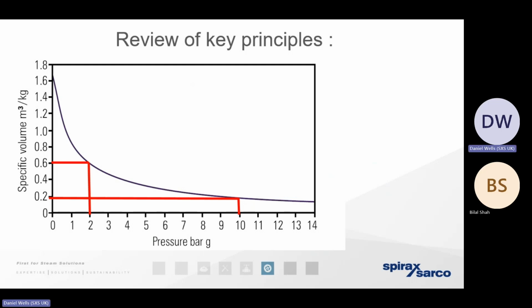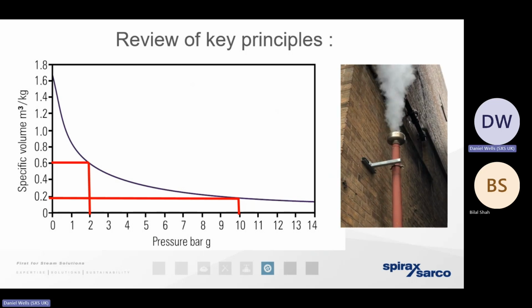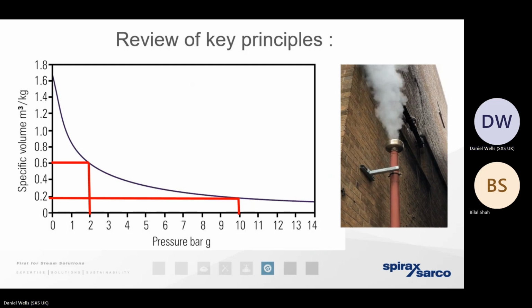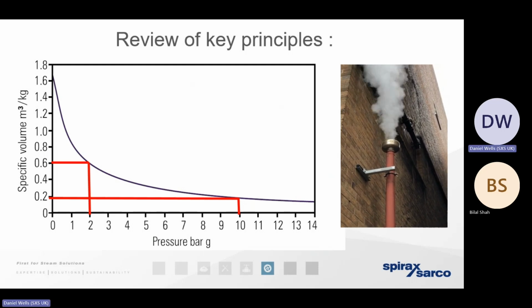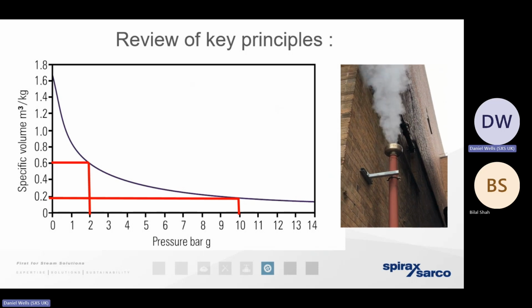The problem we're going to have is if a steam trap fails in the open position, the pressure drop can be far, far greater than we're expecting. So we're going to get very high pressure steam with a small volume, depressurizing and expanding to a huge volume. That condensate pipework's been designed to move a single phase non-compressible fluid. So if we've got a huge expansion going into that very, very small pipe infrastructure, it's going to create a lot of damage. So we're going to see what we call steam vents sited periodically around the infrastructure. The purpose of those steam vents is to prevent that damage from taking place.